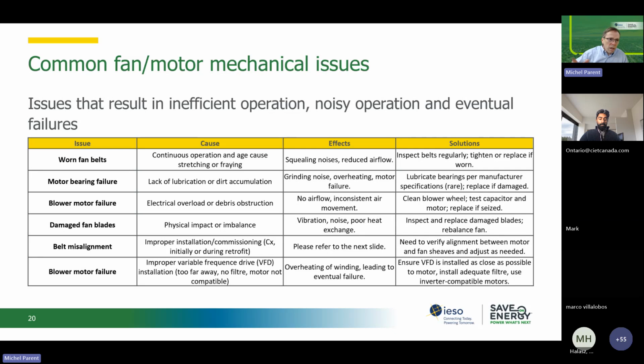There's other potential issues if we look at fan motors, and some of those will actually apply to pumps if they are belt driven, even though most pumps are direct driven. But there's a bunch of issues that need to be part of your PM program when we talk about belts. Your PM program will have change the belts. Most people will change the belts, but there's other things to look for.